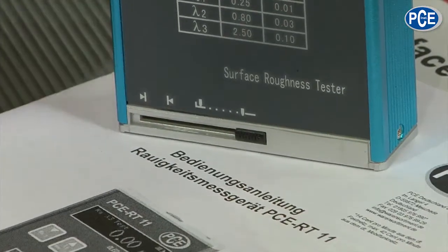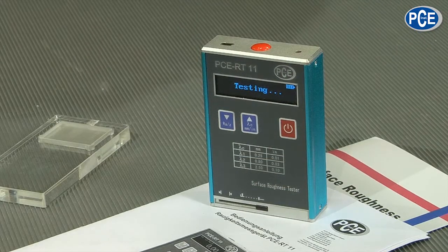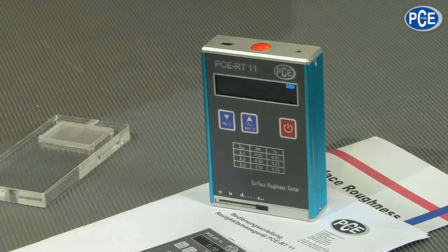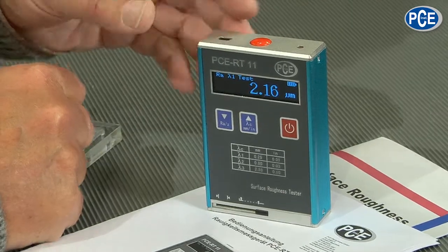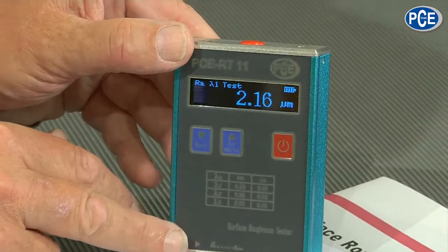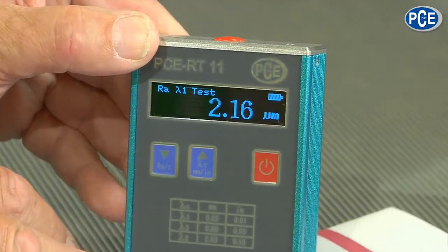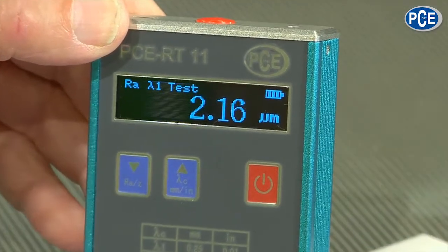Now I put it on here, start the start button, then it takes 6 seconds. It goes along this measuring area and reads the measured results, the bumpiness of the probe. And when it is finished, it will show the results. As you can see, it has beeped, and we can see that we have a roughness, Ra lambda 1, of 2.16 micrometers.